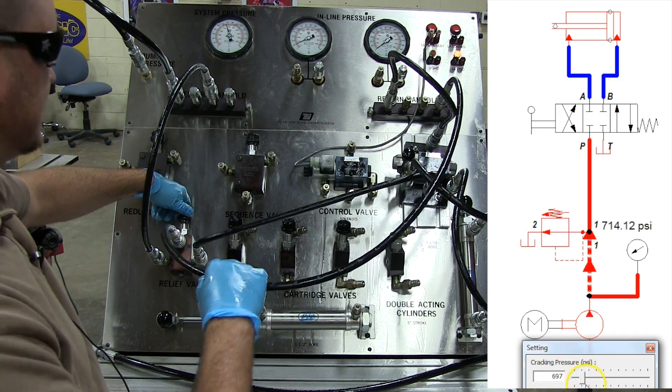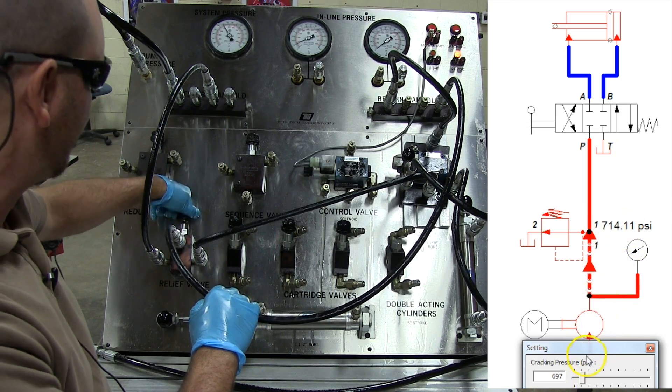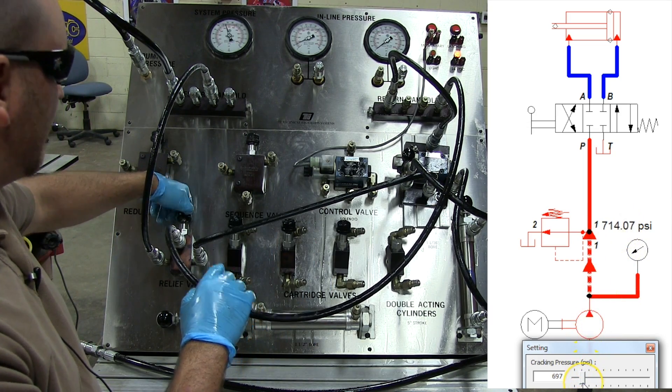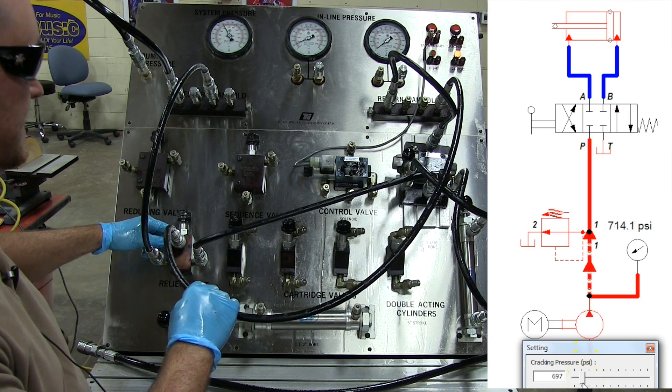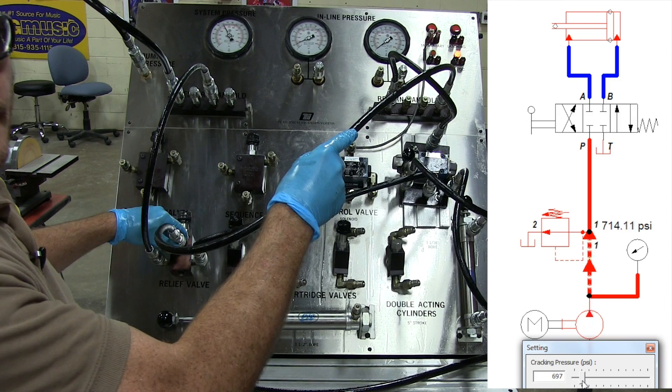And what happens is because the pump has to create flow, it absolutely always has to create flow. It's creating just enough flow to overcome this biasing spring and send that oil back to tank.